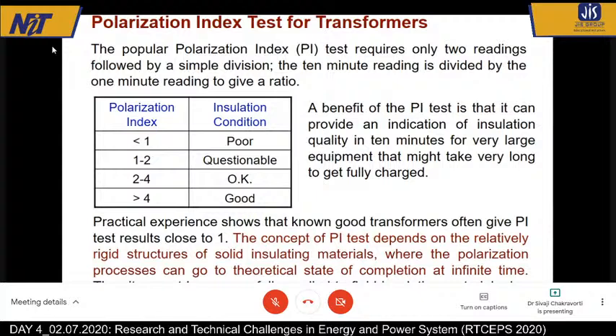This is a table given by Megger, that for a transformer, if it is less than 1, it is very poor condition. If it is 1 to 2, it is questionable. 2 to 4 is okay. Greater than 4, good. But once again, if you talk to any power engineer, they will tell you that for a real-life transformer, this 2 to 4 is never achievable. Mostly you will get it between 1 to 2. And then we have to take a very expert decision on whether it is good or bad.